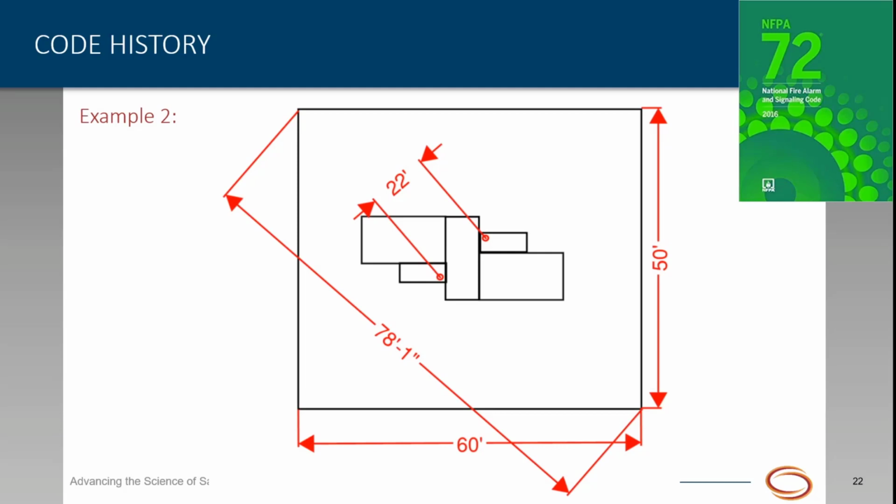In a second example, we have that same high-rise building with a 60-foot by 50-foot floor plate. Again, each floor is a notification zone in this case. We calculated our diagonal at that 78 feet 1 inch. But in this case, we have a center elevator shaft and lobby with common electrical rooms adjacent to the stairs at the center of the floor plate.